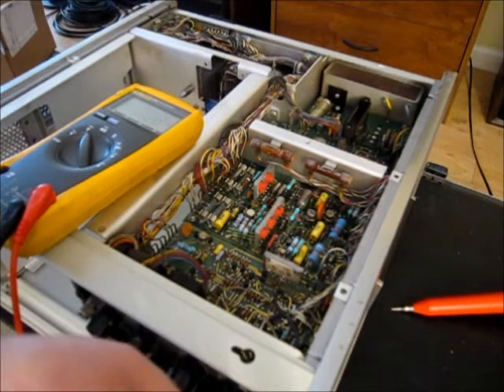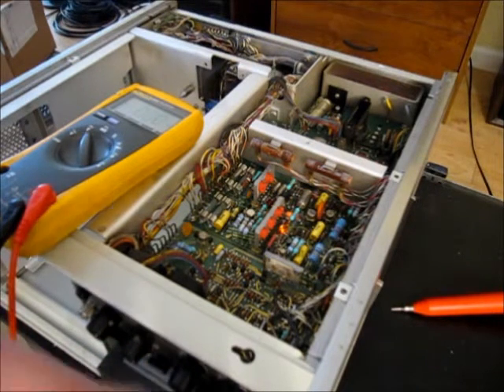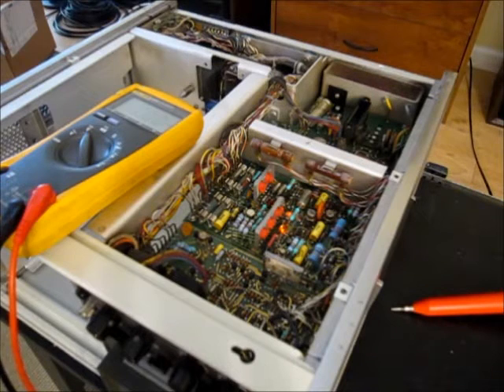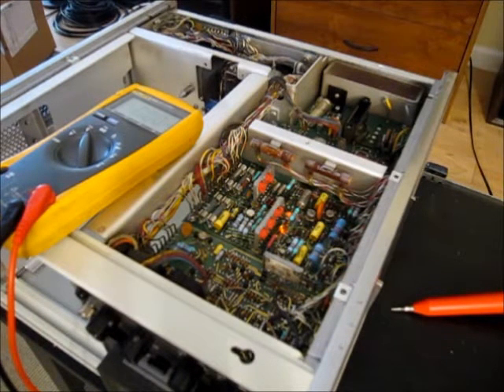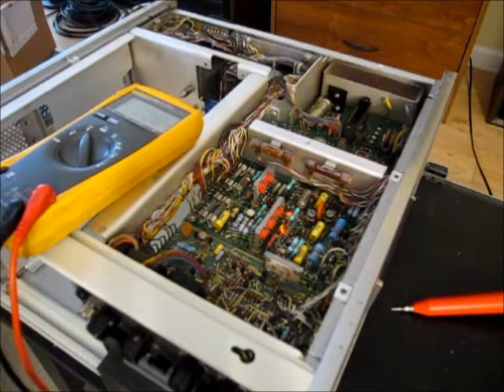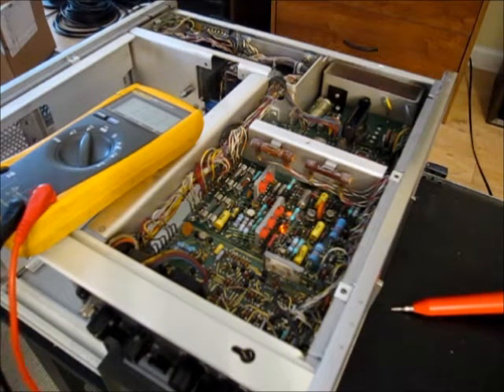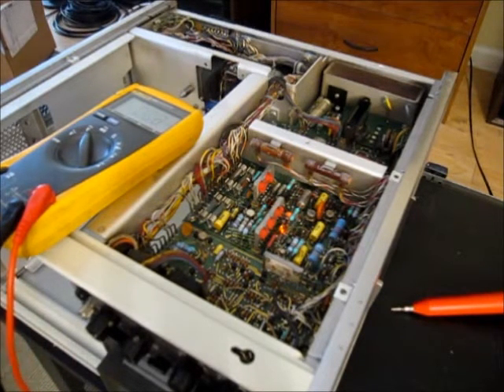So we're going to begin by powering the unit on. Then normally we would give it some time to warm up before we check the power supply voltages, but I generally found that the low voltage power supplies in these don't tend to vary much with temperature, and also I know this unit works, so I'm just going to quickly check through it.